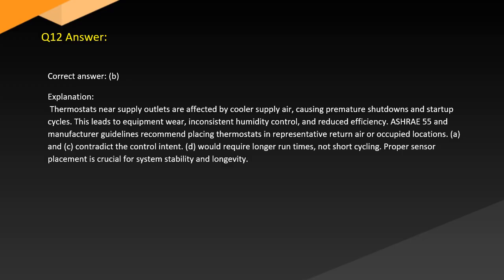ASHRAE 55 and manufacturer guidelines recommend placing thermostats in representative return air or occupied locations. A and C contradict the control intent. D would require longer run times, not short cycling. Proper sensor placement is crucial for system stability and longevity.